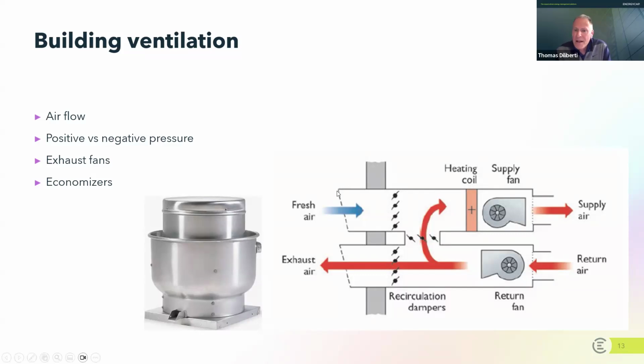So with that in mind, this represents fresh air coming in from outside into a mechanical system. These little circles with the little lines in them, if you are unfamiliar with this picture, are called dampers. So the typical flow of air into a building is through some inlet where it passes dampers. That fresh air is very likely going to pass a heating coil or a cooling coil or both. And there's going to be some type of fan that pushes that air into the building. And that's what's shown here on the top.